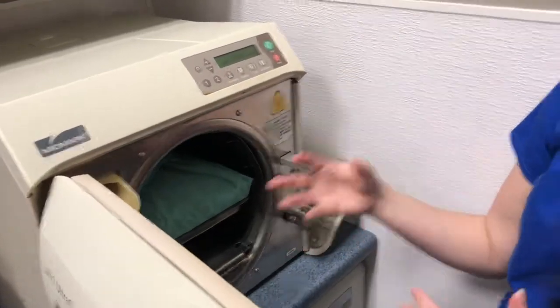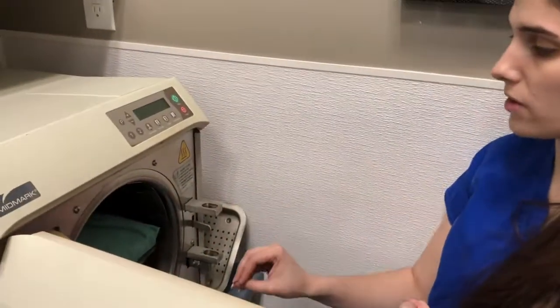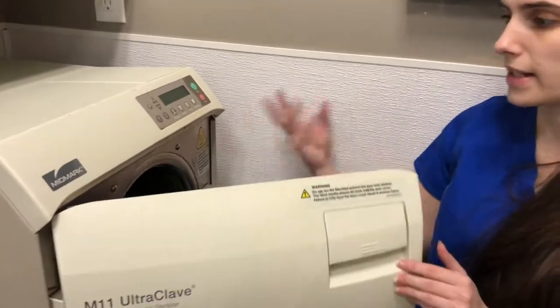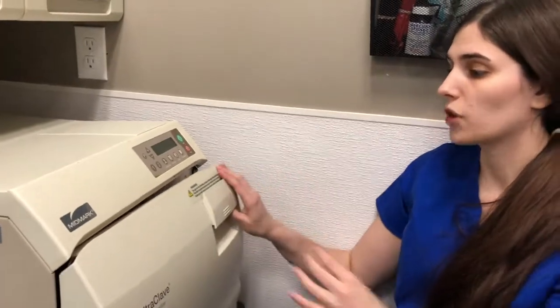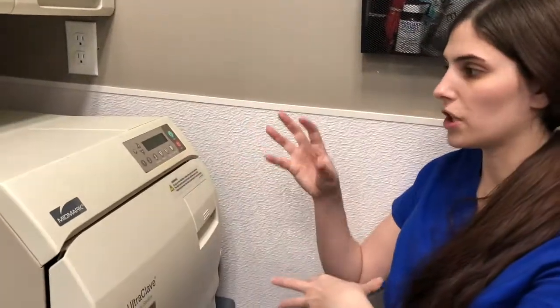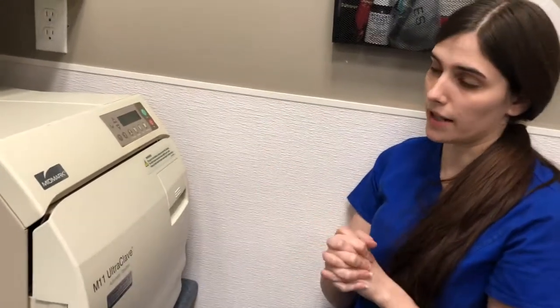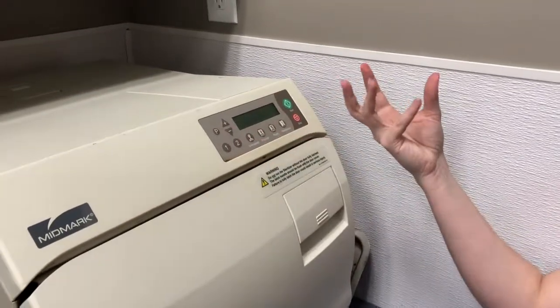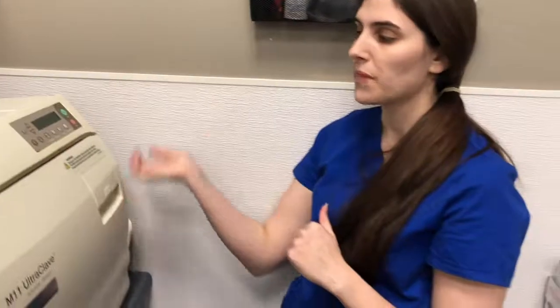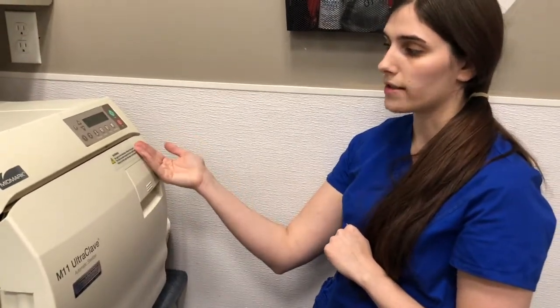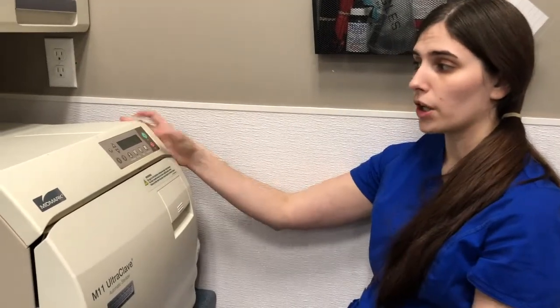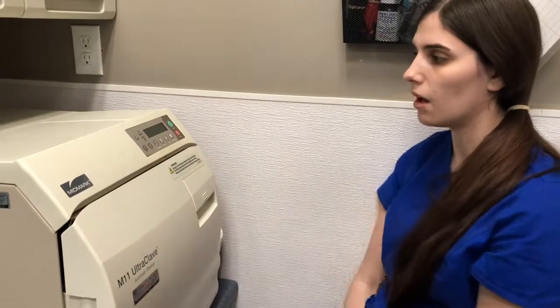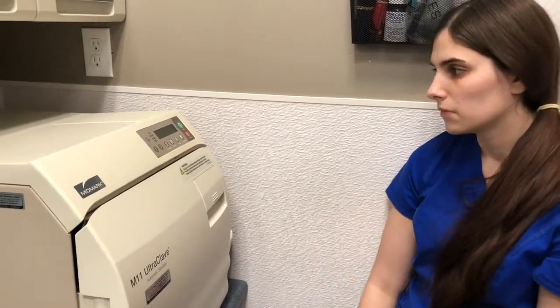In this machine is distilled water because bacteria can brew in regular tap water. So we want to make sure we have distilled water in here. And the way this machine works is by electricity heats the distilled water and creates steam. The steam creates pressure. And with the combination of heating to about 250 degrees Fahrenheit and the pressure, it is able to clear any bacteria that is in there. So if I were to start my packs, I can see that this is going to reach 250 degrees. It's going to take about 30 minutes to probably reach that temperature. And then once it reaches that temperature, the door itself will open a little bit and it will steam out and vent out itself. So if I were to start this, this is now filling the chamber with steam. It does take some time, but this will let us know once we're all done in about, I think total about an hour. But that is how we sterilize our instruments here.